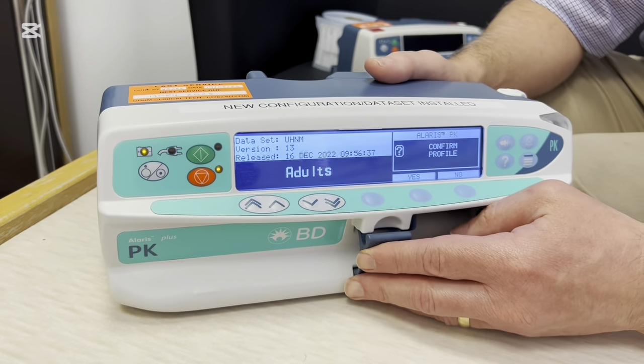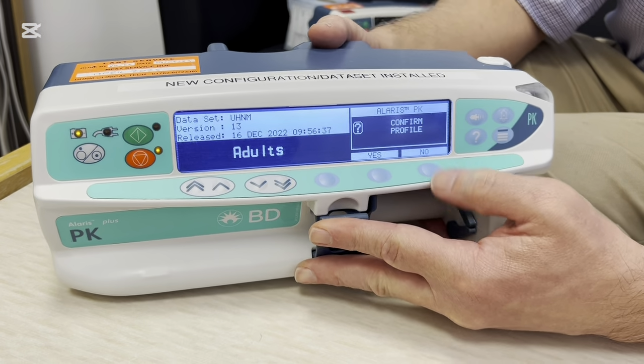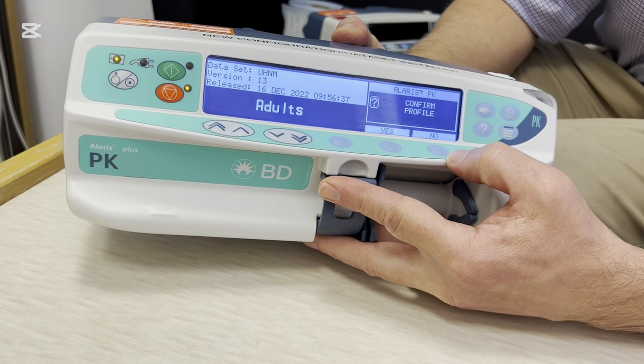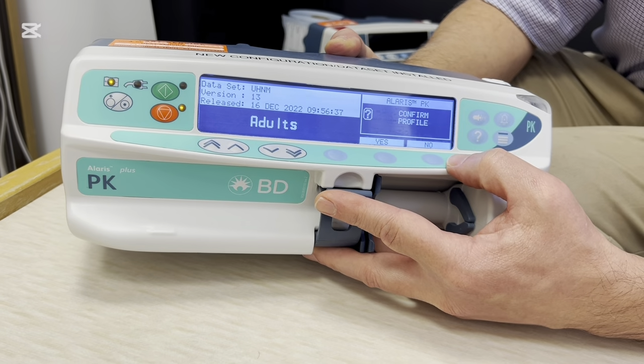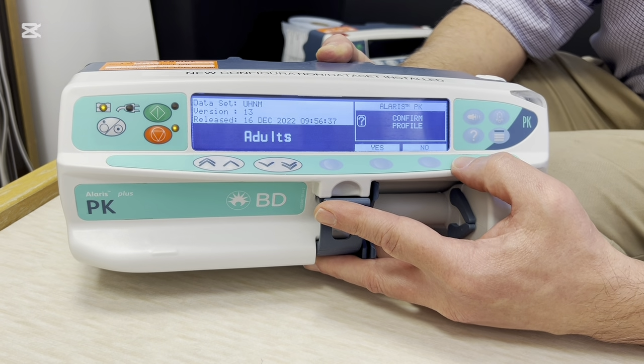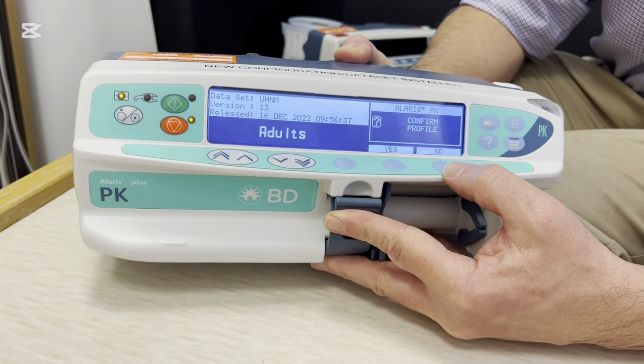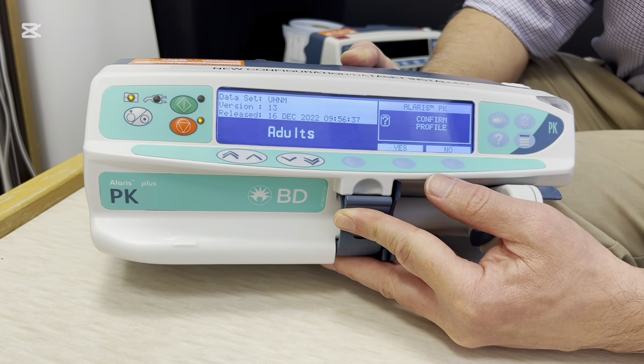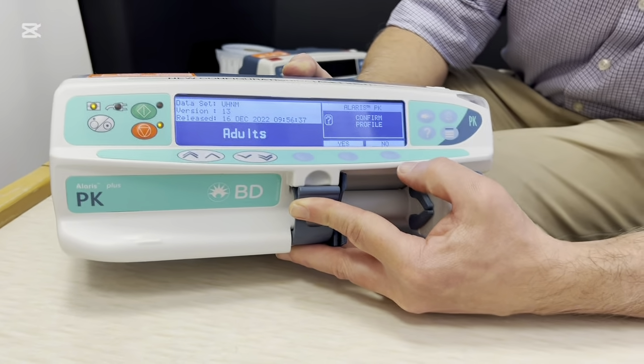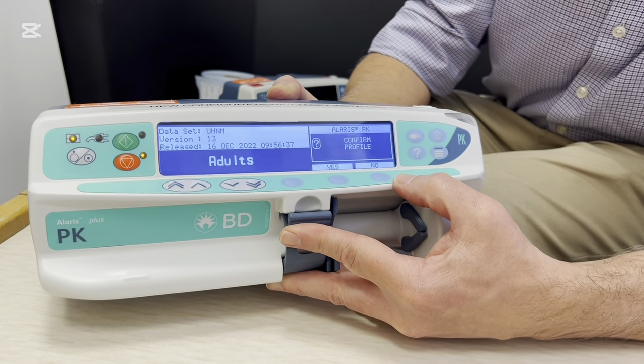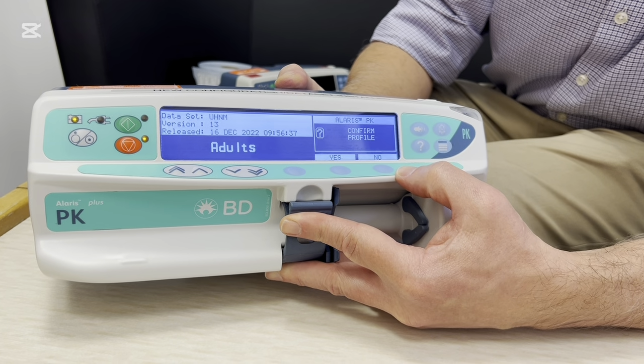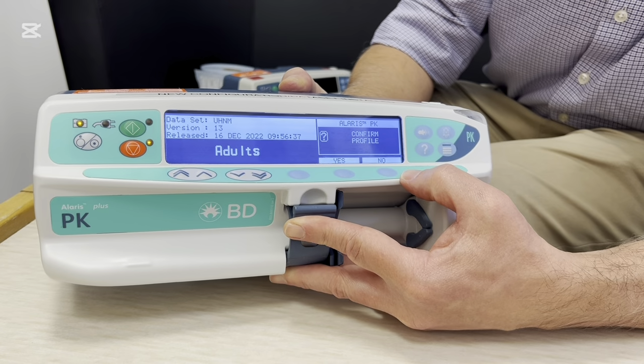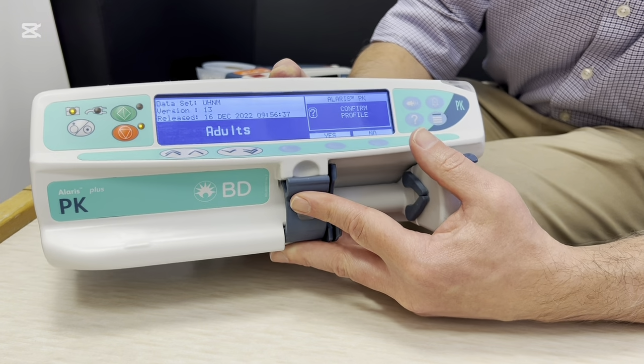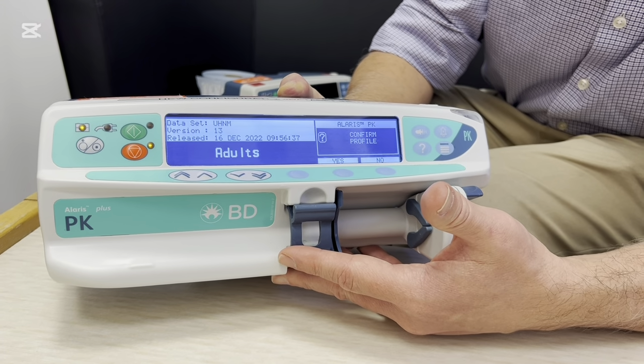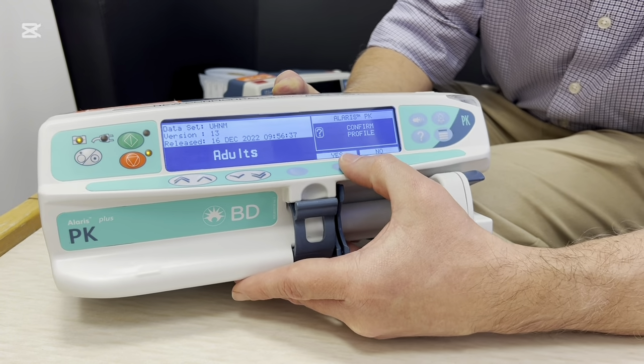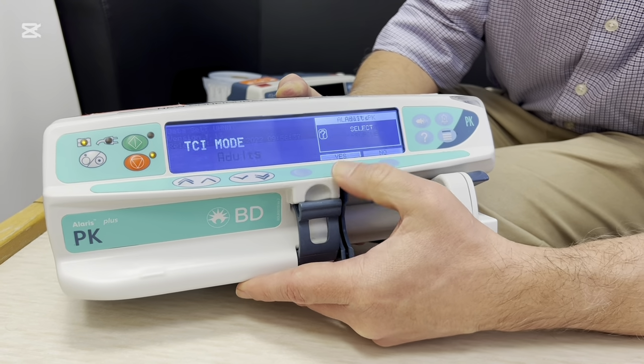So these pumps can be used for target controlled infusions, or they can be used as a standard infusion pump. I would suggest that these are only ever used in target control mode, because the temptation is if you use it as a standalone standard infusion pump, then you continue that infusion into recovery, and then there's a risk that we then lose these pumps to a ward where they may not be aware of their special powers and properties. So with that in mind, we're going to confirm it as a PK pump and use it in that mode.